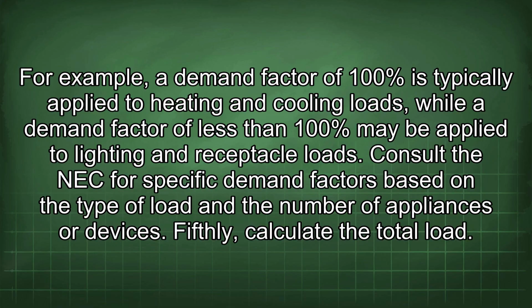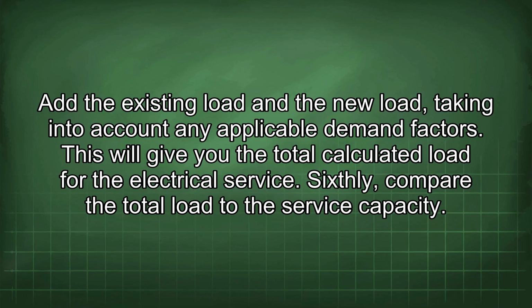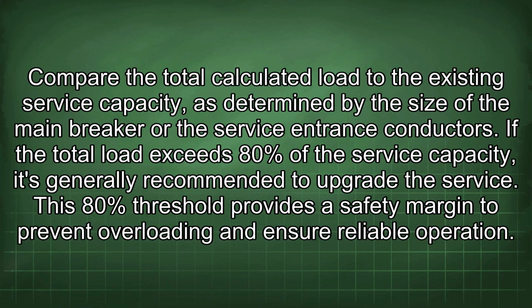Fifthly, calculate the total load. Add the existing load and the new load, taking into account any applicable demand factors. This will give you the total calculated load for the electrical service. Sixthly, compare the total load to the service capacity. Compare the total calculated load to the existing service capacity, as determined by the size of the main breaker or the service entrance conductors. If the total load exceeds 80% of the service capacity, it's generally recommended to upgrade the service. This 80% threshold provides a safety margin to prevent overloading and ensure reliable operation.